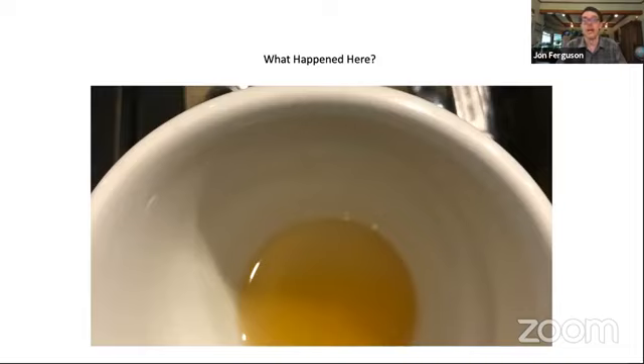So I guess the recommendation, other than draining and cleaning out the boiler to prevent this from happening, is to just get rid of the soft water kit and get a different filter. What's the corrective action here that you can take?